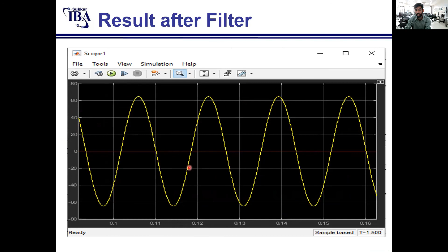So, the conclusion. This work played a tremendous role in letting us know about the different strategies applied to the series active power filter, with its importance in mitigating voltage harmonics from a system. We verified two distinct models: the grid connected system with the nonlinear load, and the grid tied PV or hybrid system. We learned about nonlinear loads and their characteristic of impacting a power system with different interruptions. In this thesis work, the control strategy of the series active power filter is a hysteresis controller. We also reviewed a variety of papers where we learned about other filters and designs. The series active power filter is chosen over a parallel active power filter due to its improvement in power factor as well. We aim to verify many different and diverse models with our designed filter.